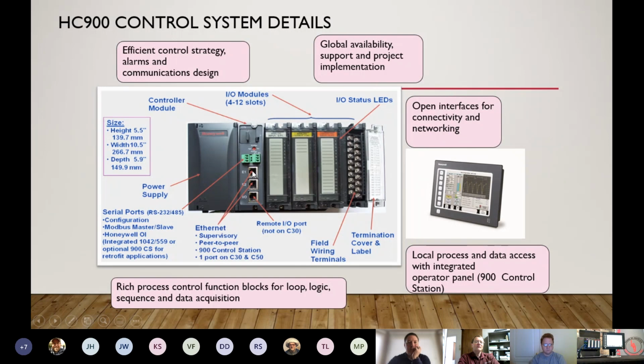Depending on the version of the CPU, you'll get 1 or up to 3 different Ethernet ports. Then on a C30, you'll get the 1 Ethernet port. This is dedicated for an operator interface if you want that as an option, which is displayed over here on the right-hand side of the PowerPoint. The middle one here is another Ethernet network port, and you can take that out to a DCS system if you wanted to, or a SCADA like Experion or SpecView, or some other SCADA system that will be hooked up to the network on a computer, either in the engineering lab or in an operating room or whatever it might be. Wherever they have that PC where they want the interface to look into the system or into the process, they can have that hooked up to the E2 port.